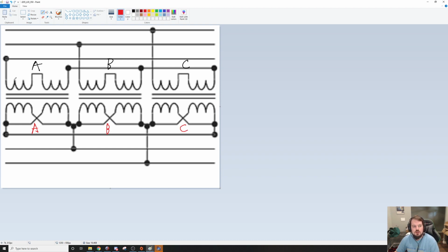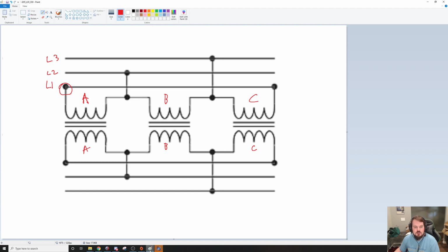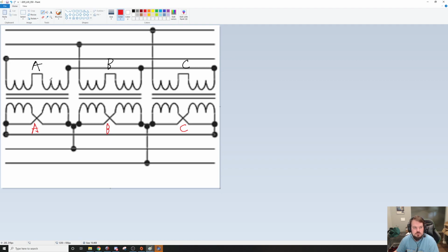But if you look, there's 2 coils. They split the coil from this drawing. So this is a single voltage or single coil. What they did is they took right here and split it into 2 separate coils. And the way you connect those 2 coils together determines high or low voltage.